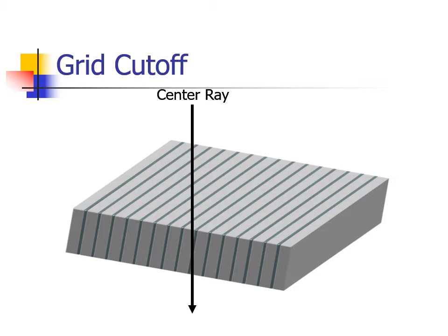Not only this line would be stopped by the grid, all of the primary radiation would be stopped by the lead in the grid as well. If the central ray were angled across the grid, the same thing would happen. This problem is called grid cutoff, where the grid stops the radiation that should normally reach the image receptor.